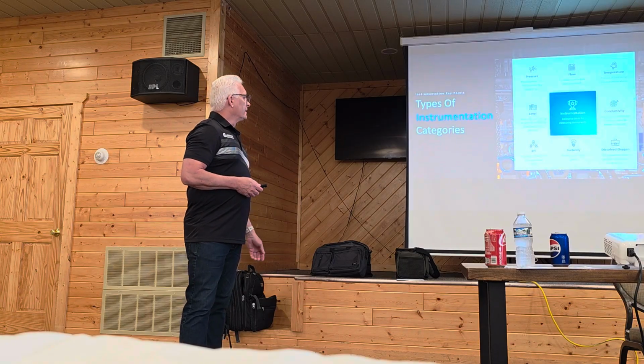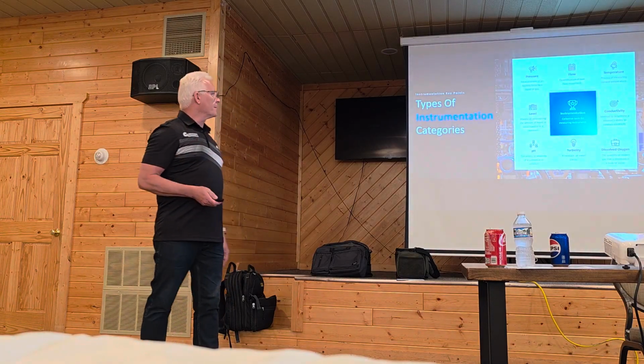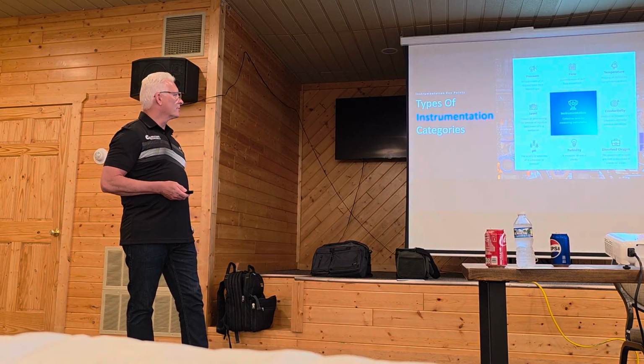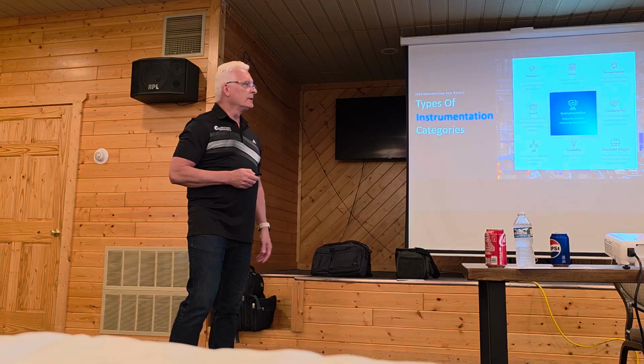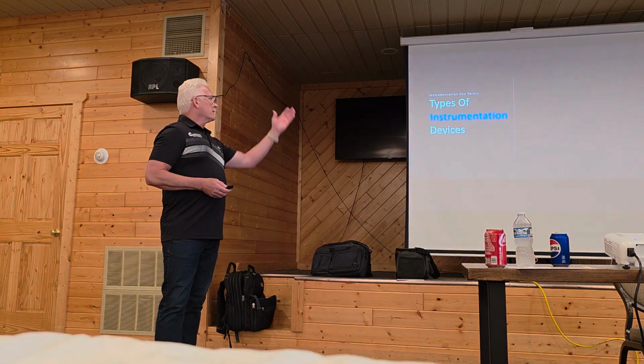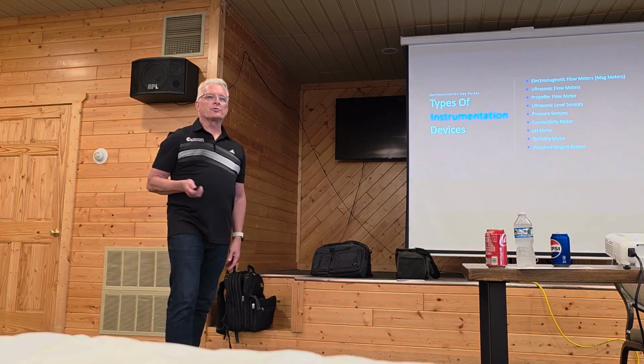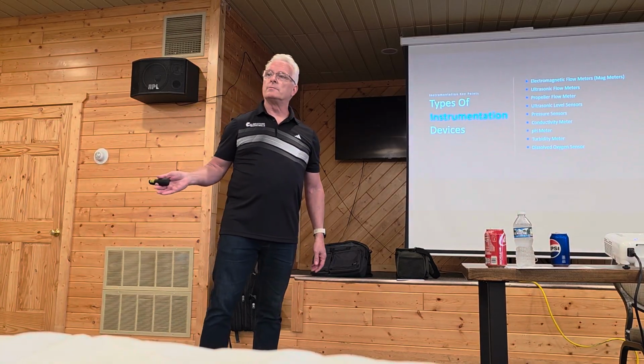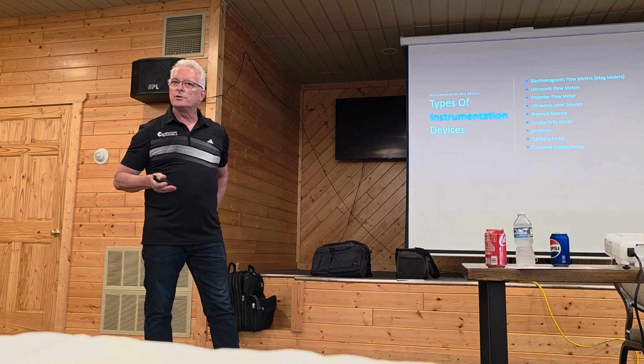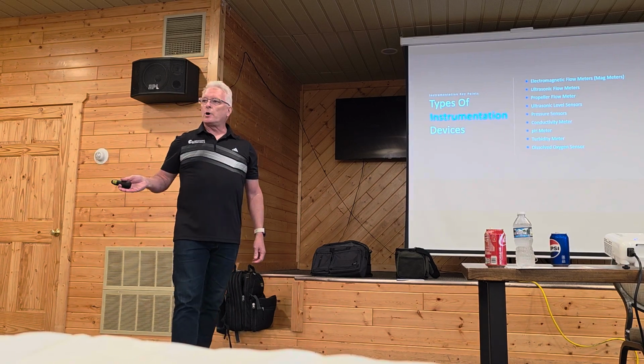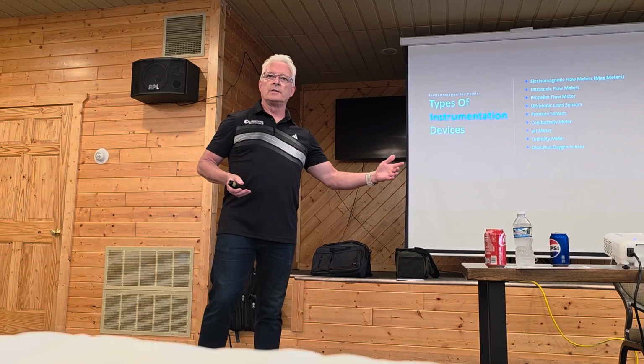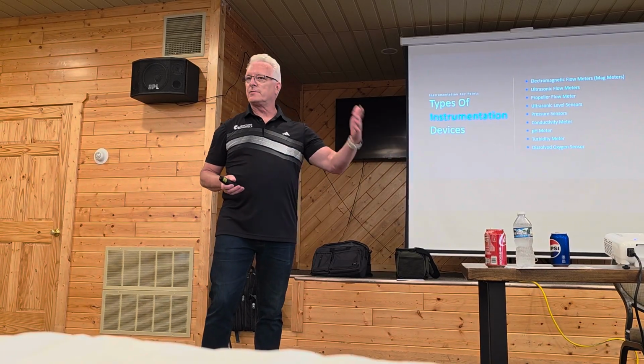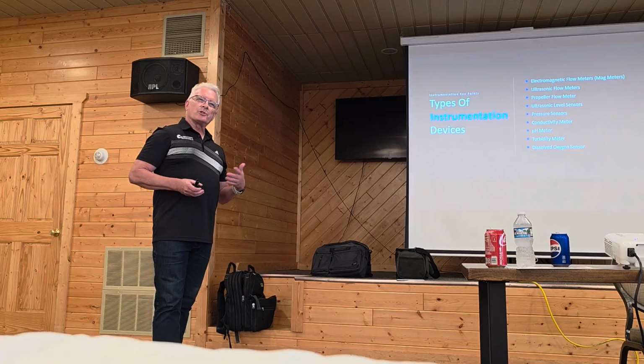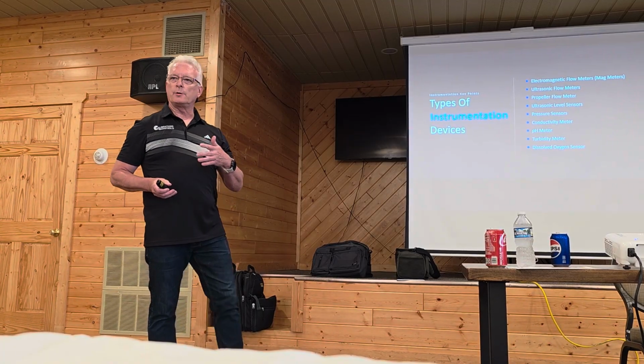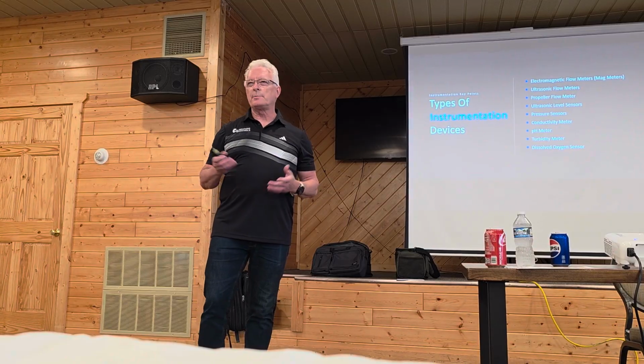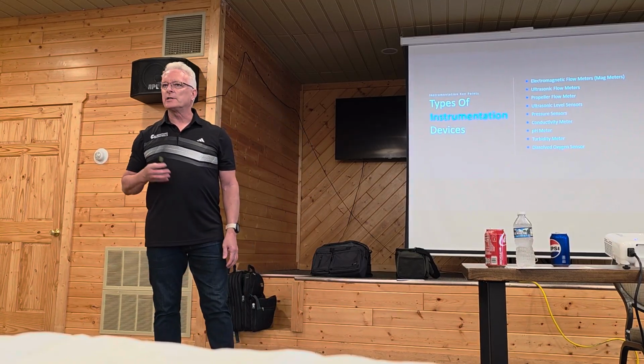And this is some examples of different equipment: pressure, flow, temperature, level, conductivity, turbidity, dissolved oxygen, DO. And then this is basically just a list of those in a different way. Ultrasonic sensors for open channel flow meters that you're usually on your influent, sometimes on the effluent too. Mag meters, propeller meters at your water plant. A lot of times the older meters are propellers because you don't want to have those on dirty water because they collect stuff on the propeller. A lot of the propellers are starting to go away as they go bad and they need to be replaced. People are putting in mag meters now. We probably do 20 to 30 mag meters a year, replacing existing meters.